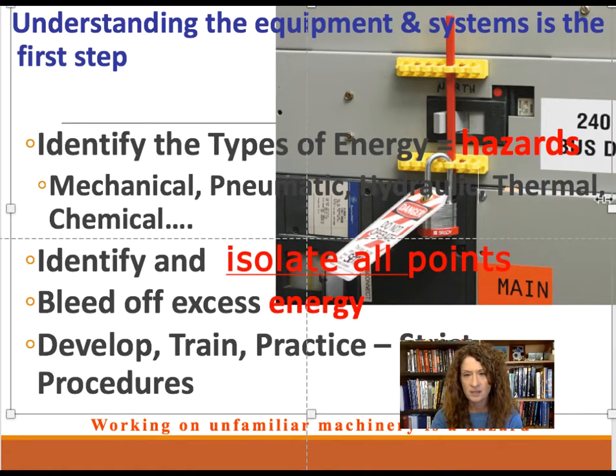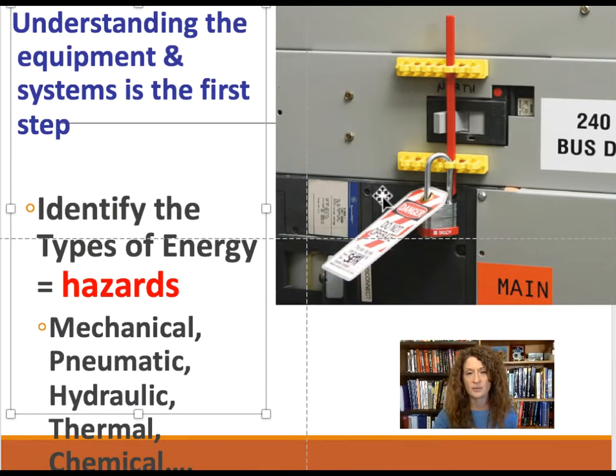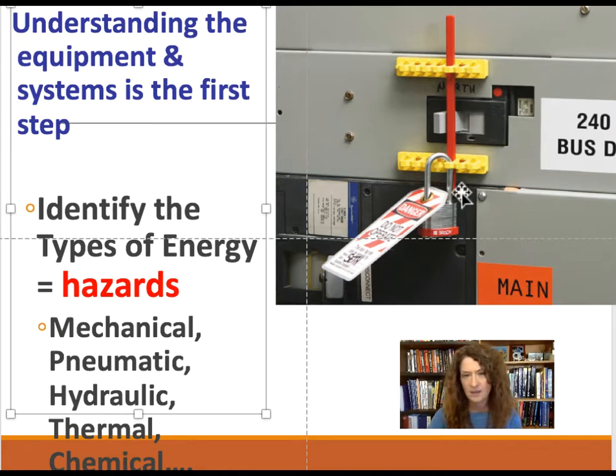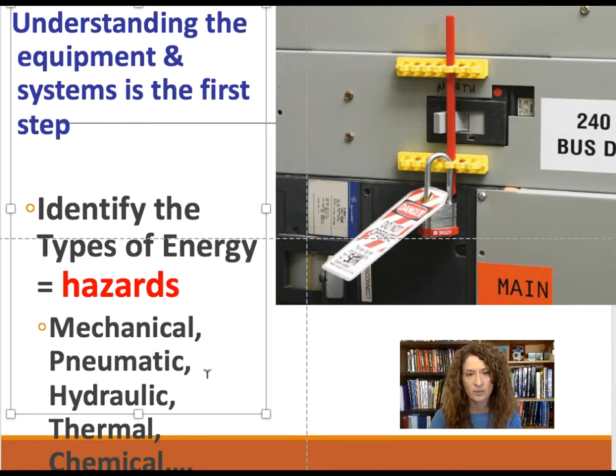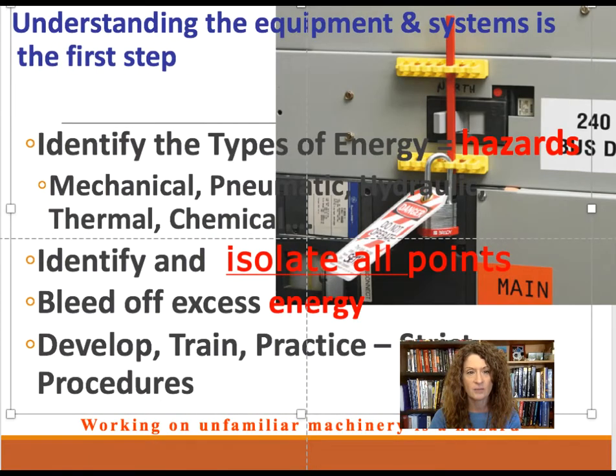Here is a really good example of something locked out and tagged out appropriately. The switch is in the off position with two connectors and a bar so you can't possibly turn it back on. A lock with a tag is in place — locked out and tagged out — and the lock is kept with the employee who is actually performing the work.